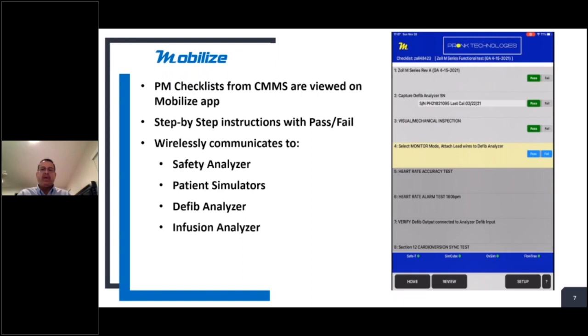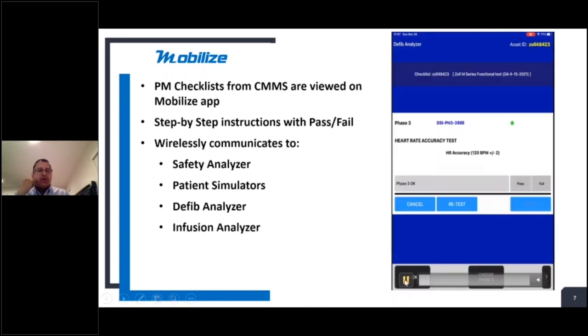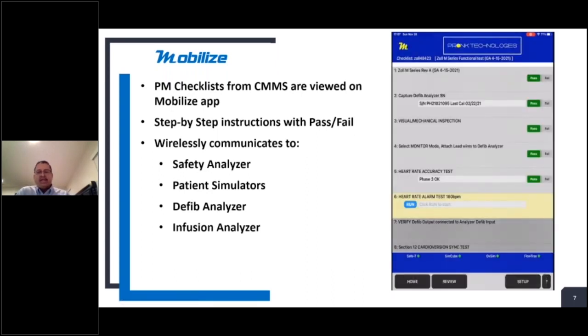The technician is following each step-by-step procedure in performing those steps. Again, here you can see there's a case where we need to check the hands-free side, make sure our heart rate is accurate. And so you have a command here back to the Phase 3 saying, hey, let's do a heart rate test. This information here is the guide for the technician to know what to do. These are all user definable in terms of what information and what targets you want to have. And then you would have the analyzer execute that test. The technician confirms that the result is correct. You would pass or fail that device, go on to the next test.